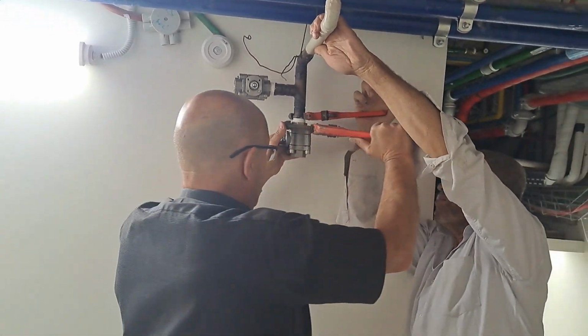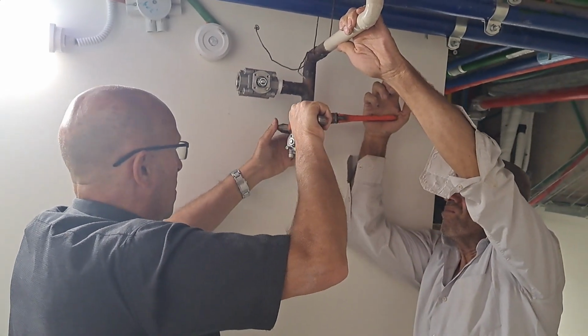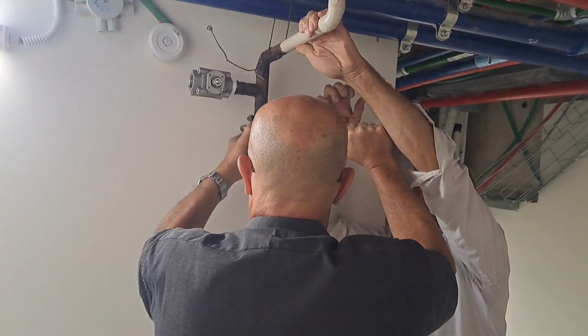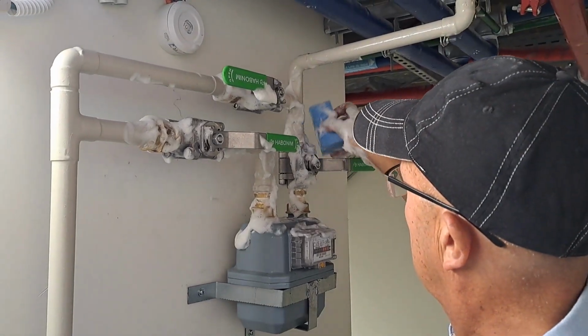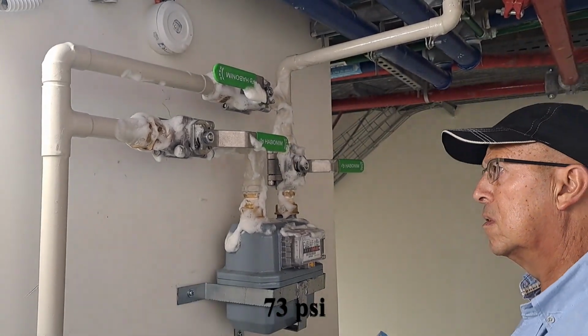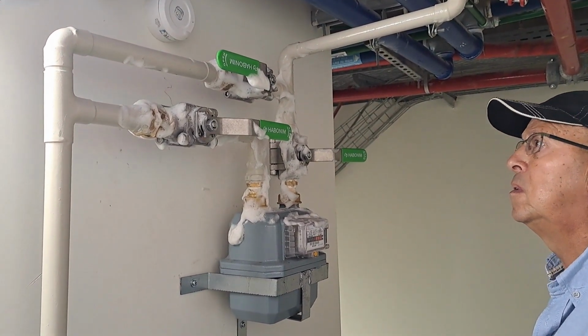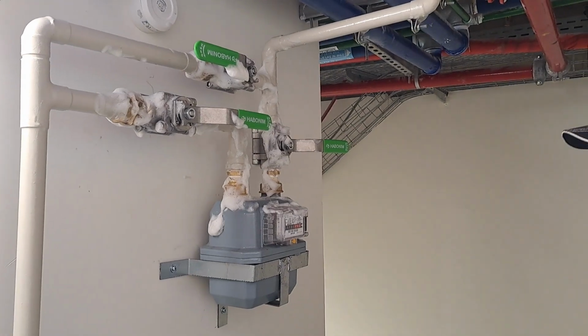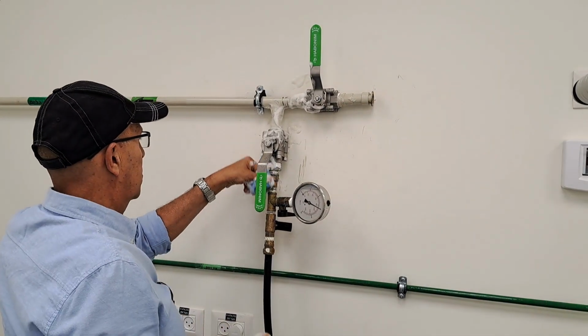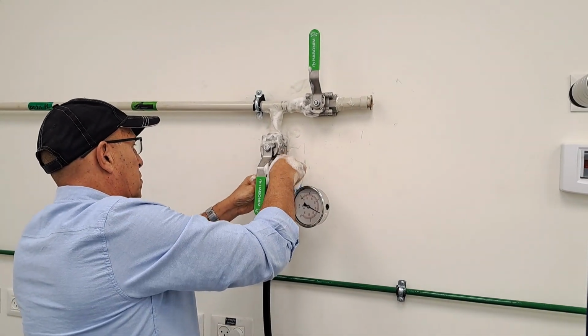Connections to valves and the gas meter are carefully tightened with Teflon tape. After installation, the system was pressurized to 5 bar of air, and all the connections are checked with soap and water. The line was left pressurized for several hours to check for leaks.